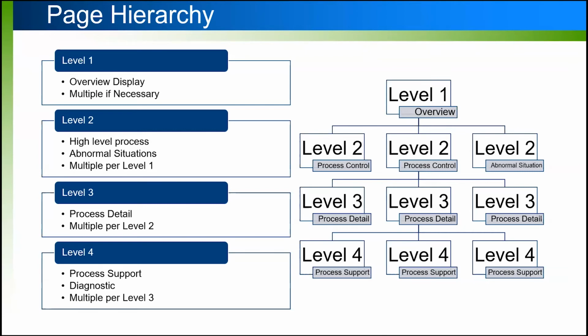The next level of screen is your process detail. Here you're zooming in on the process to look at it in more detail, with more values and more embedded trends on those screens. This is where your operators can go to troubleshoot processes. Then your level 4 screens are usually for maintenance personnel.